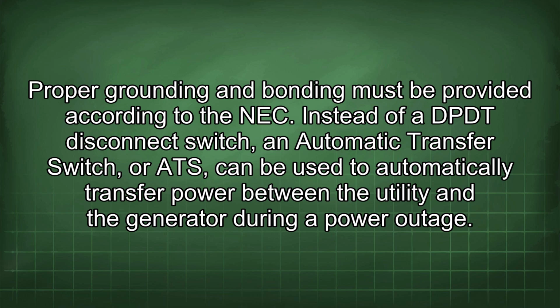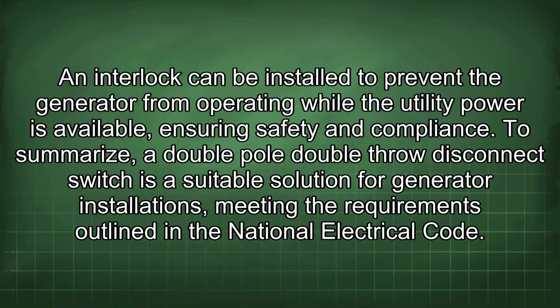Instead of a DPDT disconnect switch, an automatic transfer switch, or ATS, can be used to automatically transfer power between the utility and the generator during a power outage.